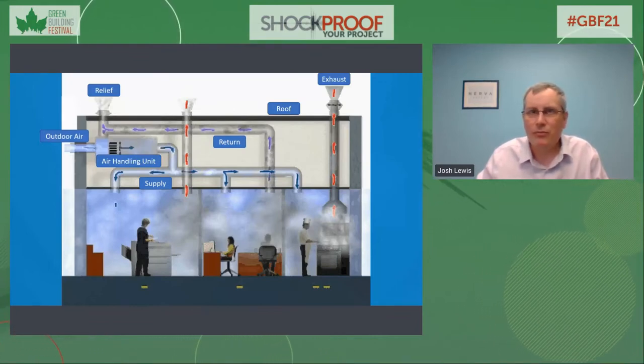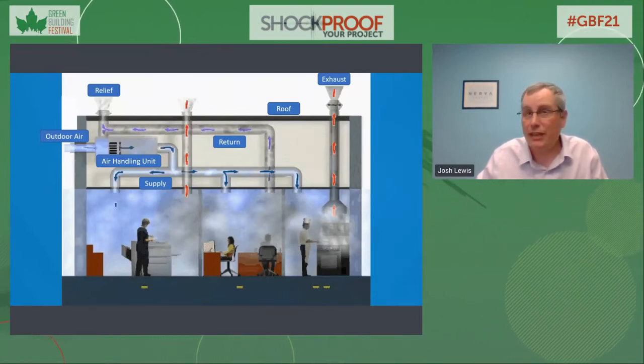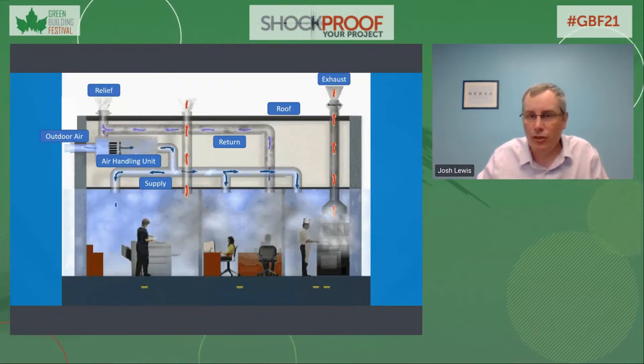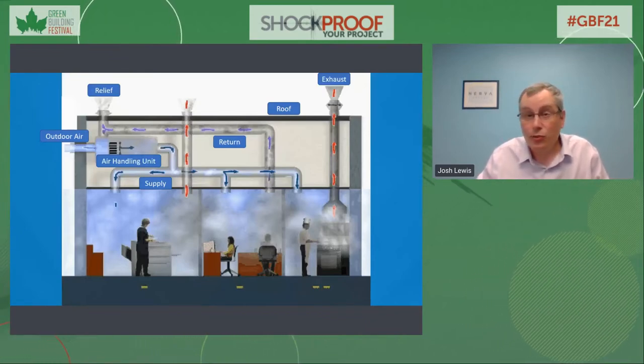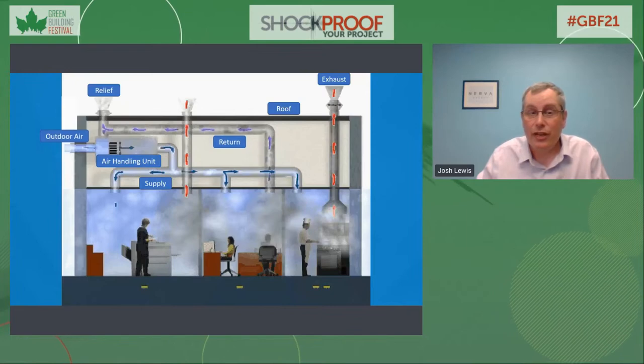Also, it's not just about improving air flow. Some buildings, especially schools, were not even designed and constructed with mechanical ventilation systems. For example, in Toronto, Ontario, at least 99 public schools have no mechanical system and rely on windows alone for air circulation. And typically they have hot water radiators for heating in the winter. Well, that kind of design has not been acceptable within the building code for decades. Our stock of school buildings in Ontario is quite aged, averaging 39.4 years old, with many much older than that, including some even from the late 1800s. These older buildings have likely always had less than perfect indoor air quality, which the current pandemic has now exposed.